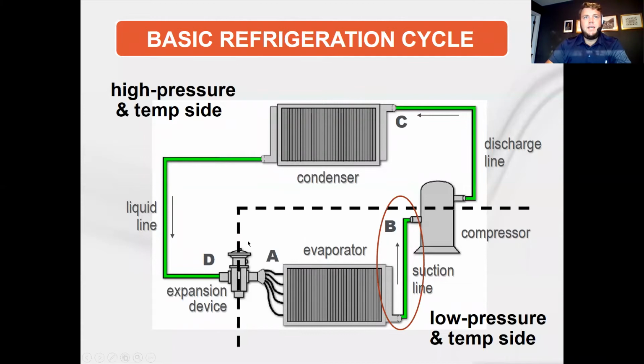back to our thermal expansion device, which at that point strictly reduces the pressure and flashes off into mixed vapor, some liquid, some gas, back into the evaporator to restart the cycle. So in the split systems that we're talking about today, most commonly the compressor and the condenser are combined into a single packaged unit, known as the condensing unit most often, or air-cooled condensing unit. And they are connected by field piping, whether it's a short length or really long length of liquid line and suction lines, to an indoor, most often indoor unit or outdoor air handler style that contains the evaporator and expansion device.